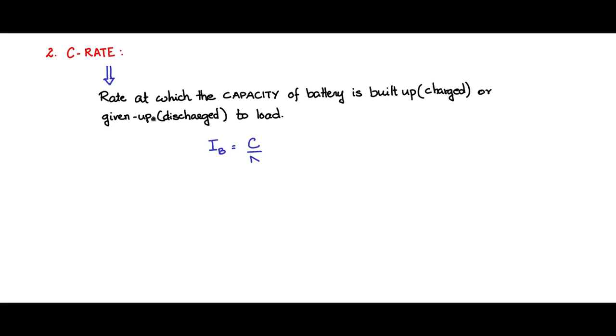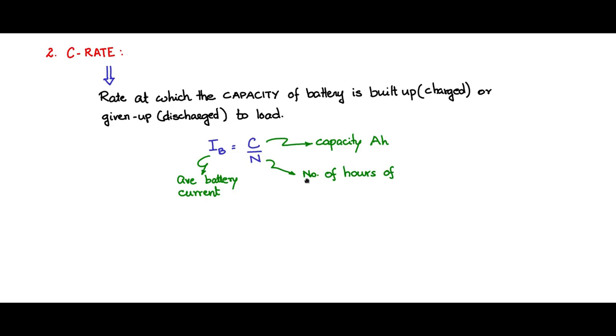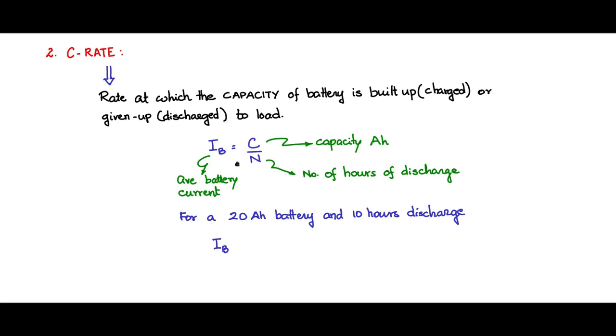We have a simple equation here: IB, the battery average current, is equal to C divided by N. C is the ampere-hour capacity and N is the number of hours of continuous discharge. For example, for a 20 ampere-hour battery and 10 hours of discharge, IB is 20 ampere-hours divided by 10 hours, which is 2 amps.